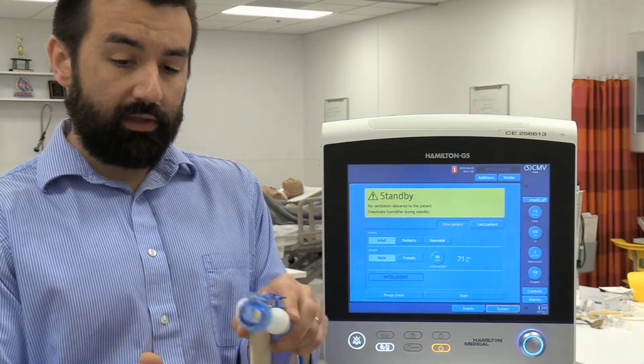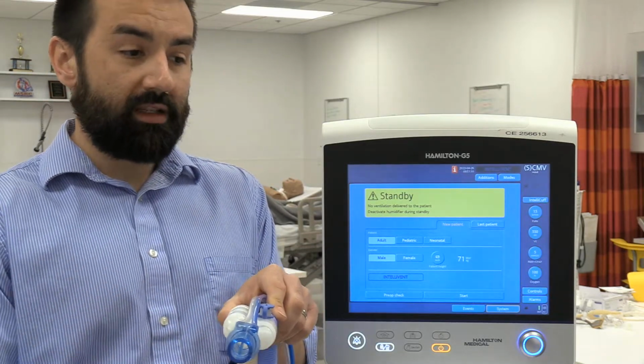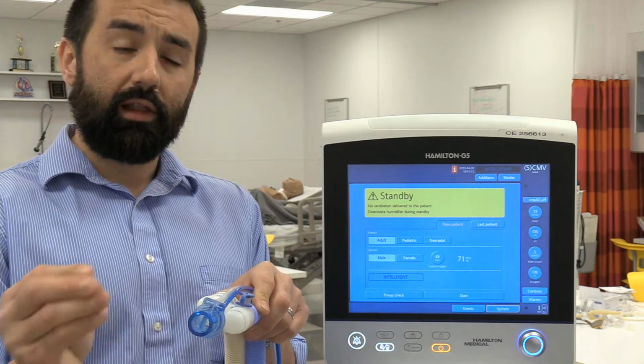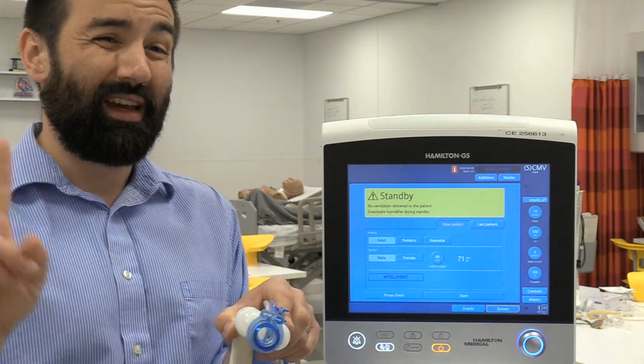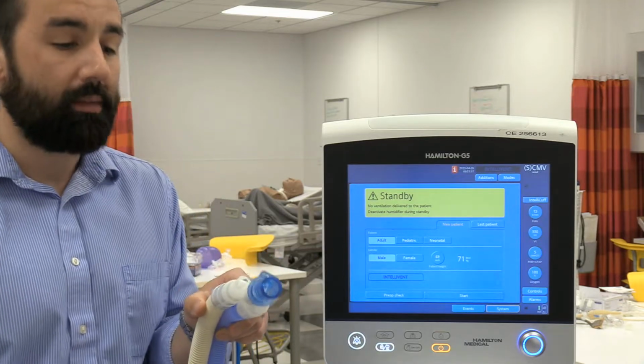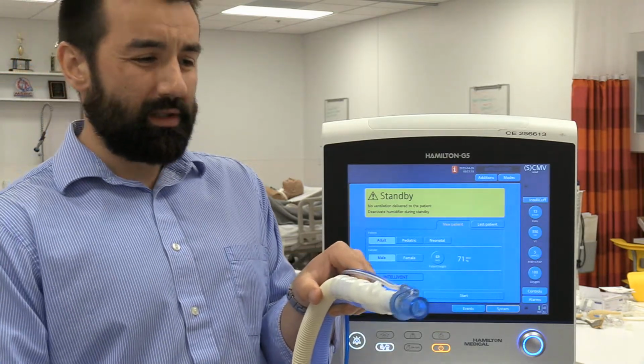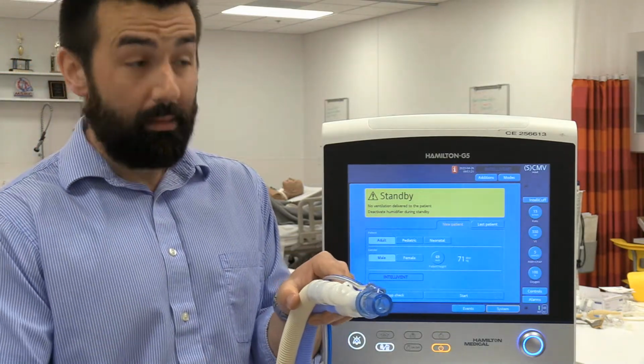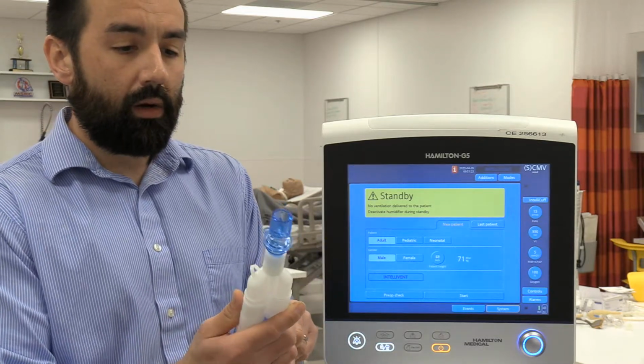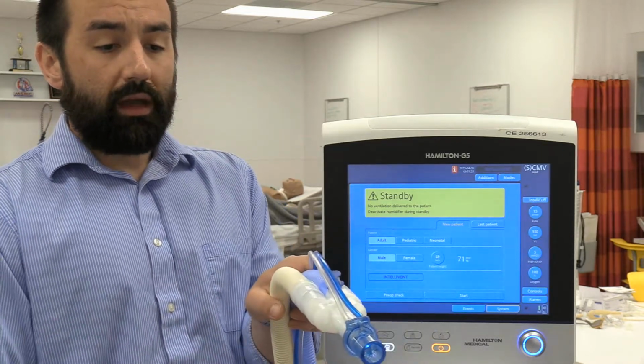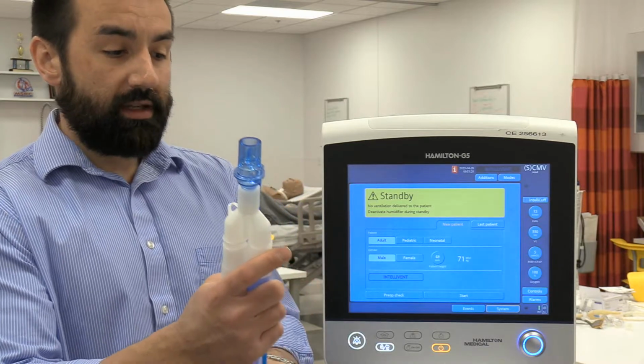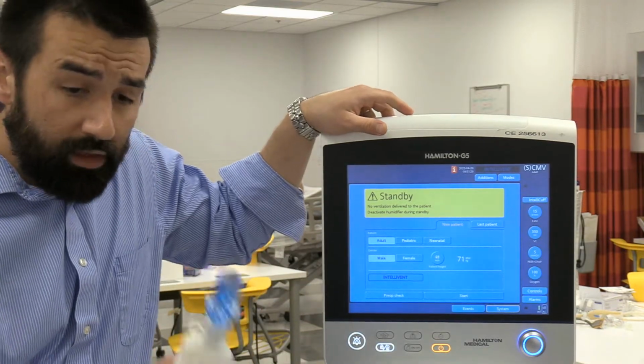By putting the flow sensor right here, we get instantaneous measurements. It does some crazy stuff with taking little micro pauses and trying to give us a pseudo plateau pressure or auto PEEP and things like that without doing a pause like we would traditionally do. I still recommend getting a hard value on that. And you can make an argument that this is going to provide for more responsive triggering abilities. So the flow sensor goes right here.